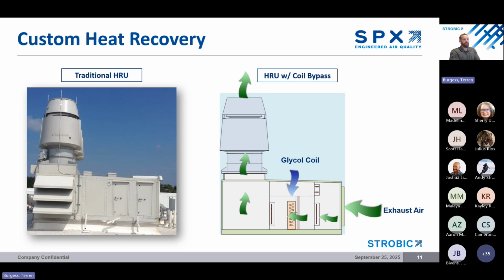Now, benefits are big, right? You're going to reduce the load on your mechanical systems. You're going to reduce your heating and cooling load, which is going to translate to a reduction in your utility bills. And second, you're going to reduce the building's carbon footprint, right? So to meet those sustainability goals and green building standards. And we've got to consider, because these laboratories oftentimes are running 20 plus hours a day, 7 days a week, these savings are substantial, right? They're not seasonal, and they're going to add up almost every day of the year.